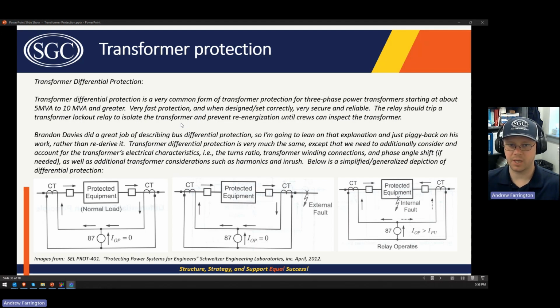Because it's so fast and secure and reliable, if the transformer differential relay operates, you know that the fault is in the transformer zone of protection. So you want to lock it out, trip the high and low side breakers, and prevent them from being closed using a lockout relay in order to isolate the transformer and allow crews to inspect it. Transformers are obviously very valuable pieces of equipment, so you don't want to re-energize them if they're faulted without having somebody inspect it. So that's why we use the lockout relay.